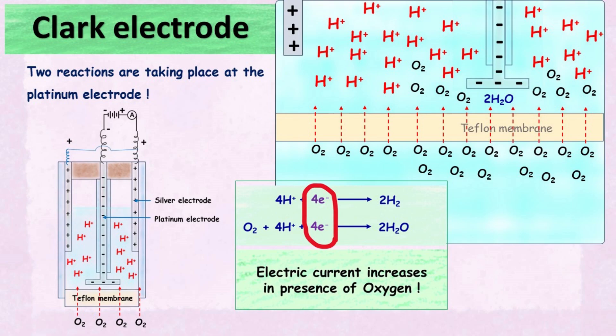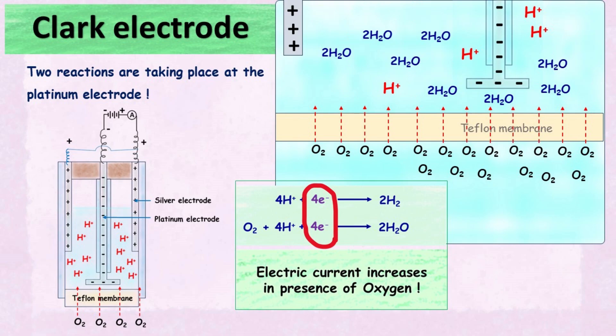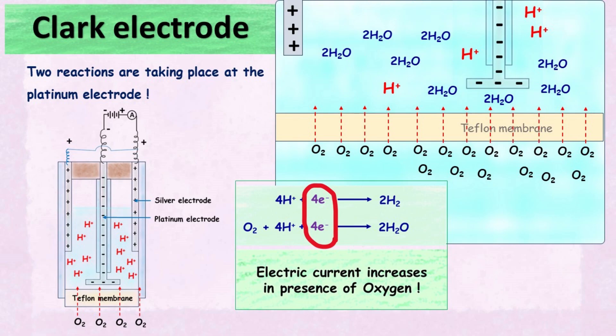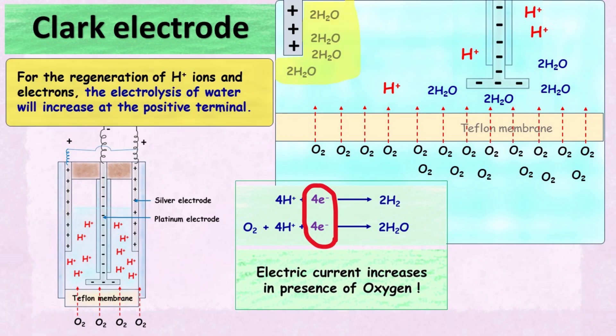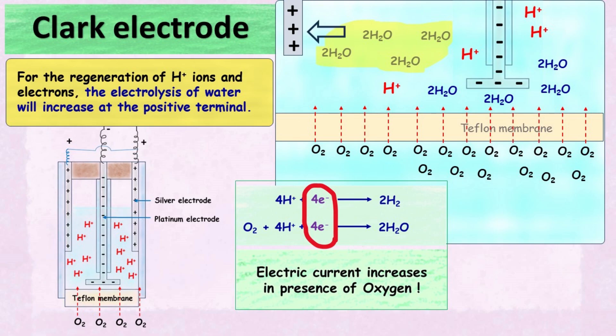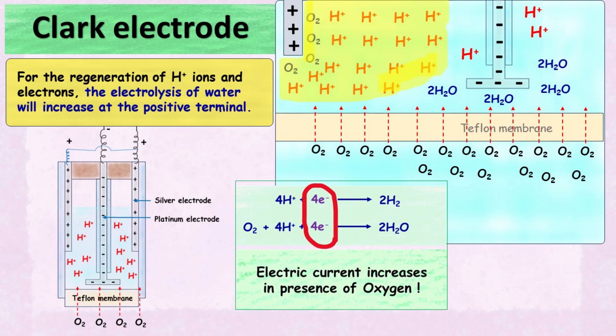You might wonder whether the presence of oxygen decreases the H+ ions in the electrolyte, but this is not the case. When oxygen consumes the electrons and H+ ions, the system tries to form more hydrogen ions and electrons. This happens by an increase in the electrolysis of water at the positive terminal, generating more H+ ions and electrons. These electrons are pulled up by the battery and sent to the platinum electrode. In short, the presence of oxygen increases the forward reaction in the electrode system, which finally increases the electric current. More oxygen means more electric current detected — and this is how the Clark electrode functions.